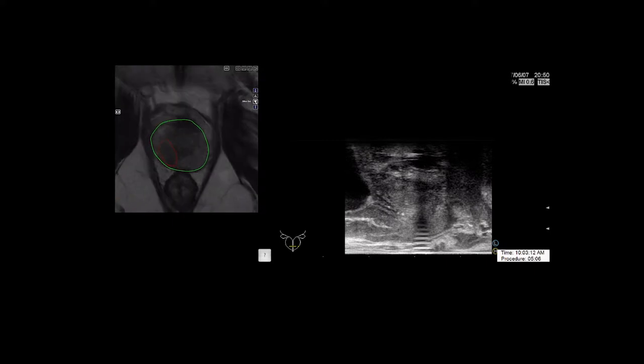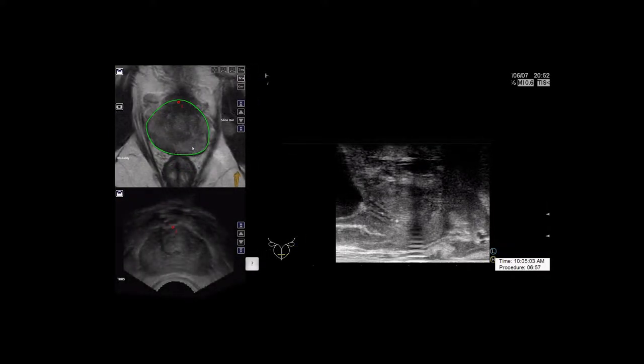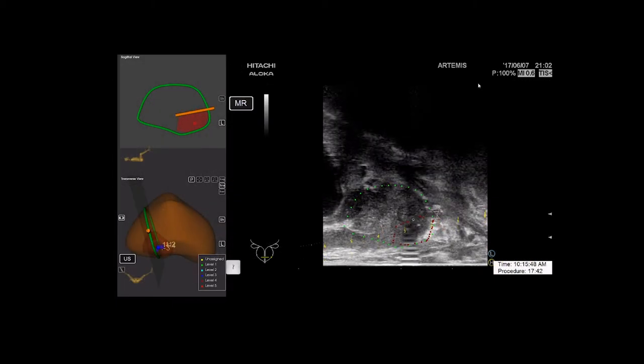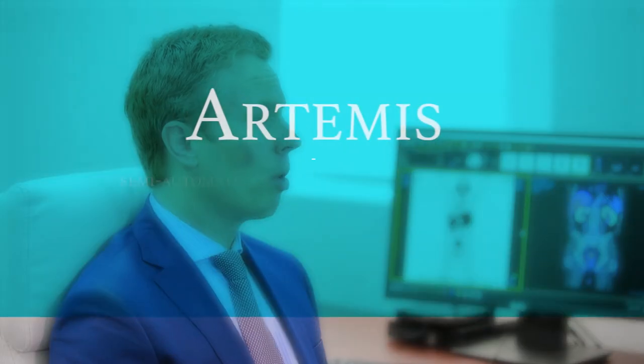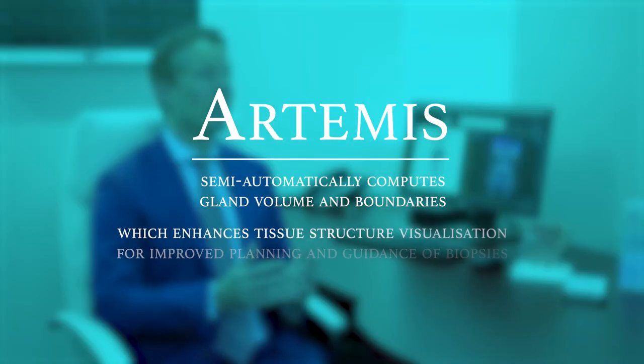Artemis is a computer-targeted device which allows biopsy site tracking with a 3D ultrasound image and full color model, and allows fusion of real-time ultrasound with a preoperative MRI. This computer targeting fuses the preoperative MRI image with the intraoperative ultrasound by overlaying the two, precisely indicating where biopsies should be taken, thus mitigating any human error.